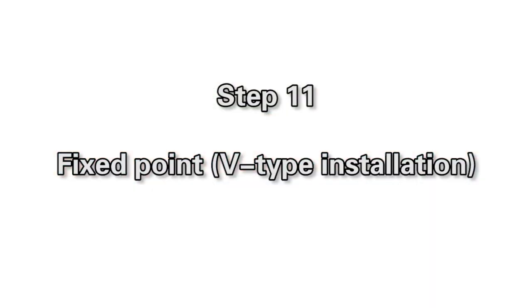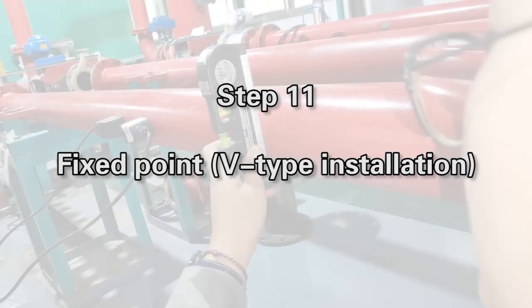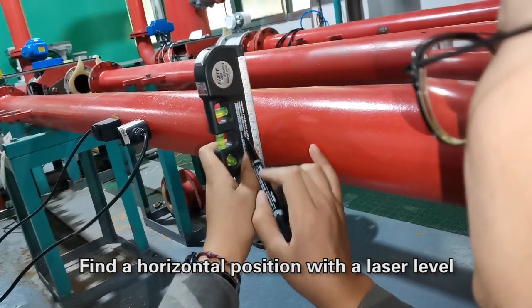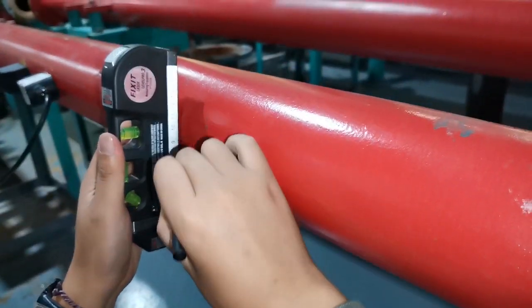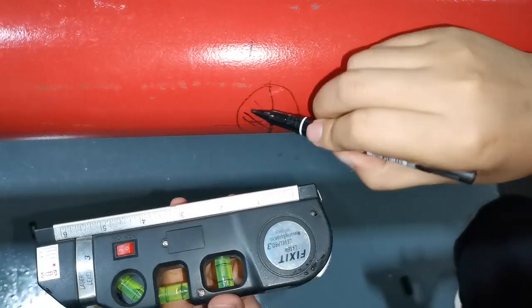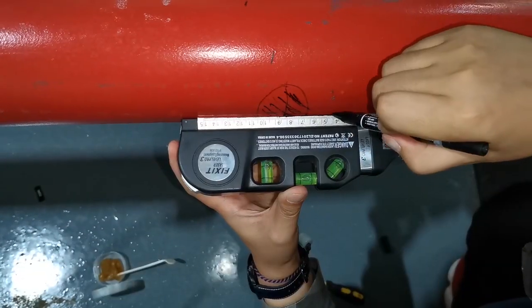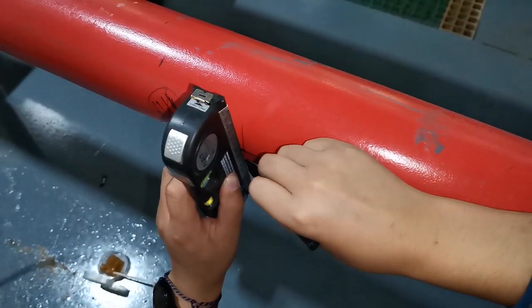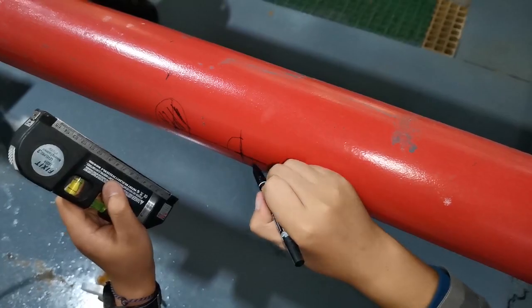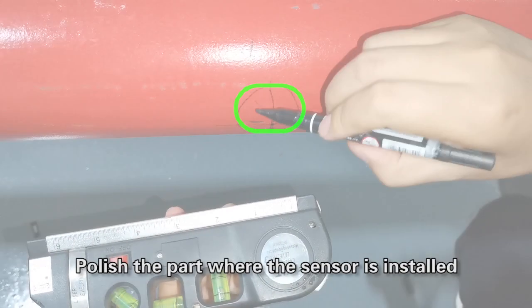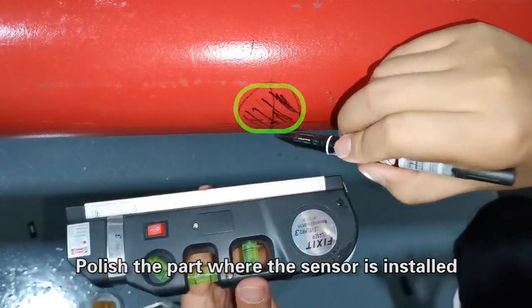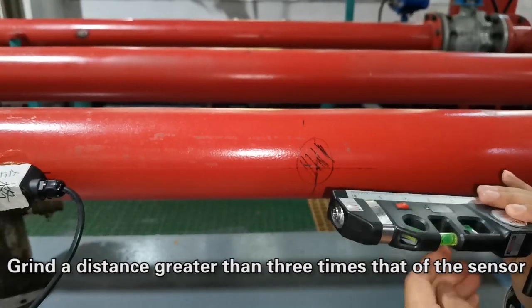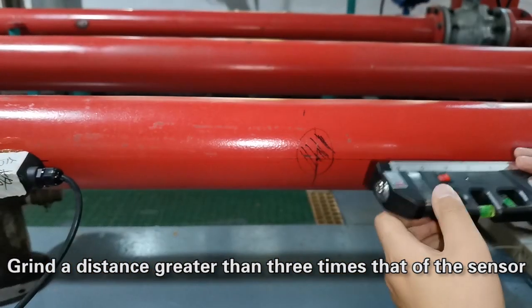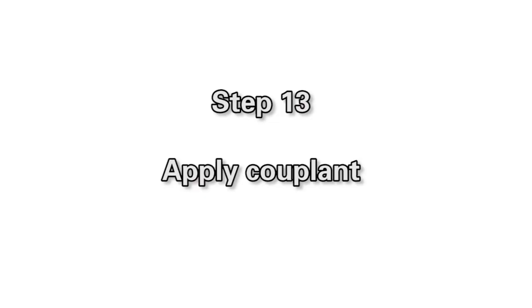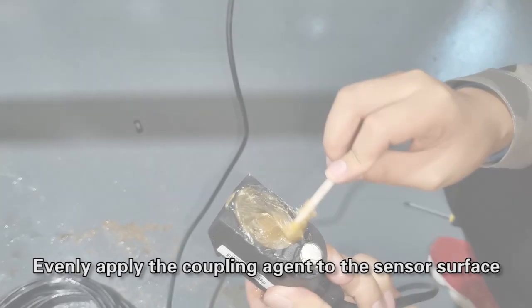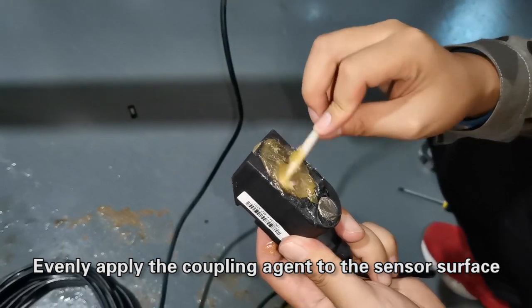Step 11. Fixed point V-type installation. Find a horizontal position with a laser level. Step 12. Derusting. Polish the part where the sensor is installed. Grind a distance greater than 3 times that of the sensor. Step 13. Apply couplant. Evenly apply the coupling agent to the sensor surface.